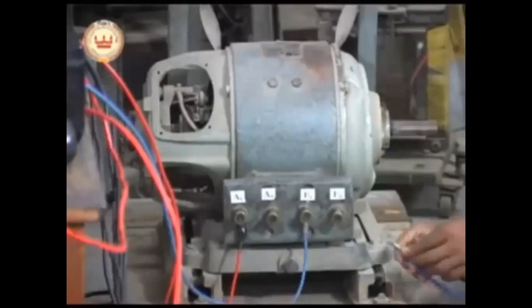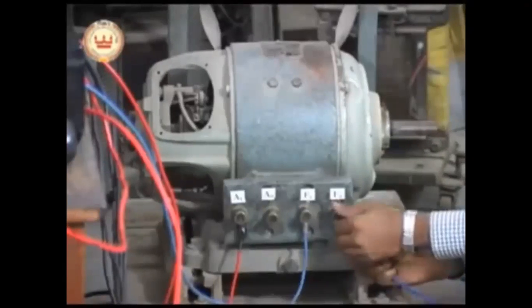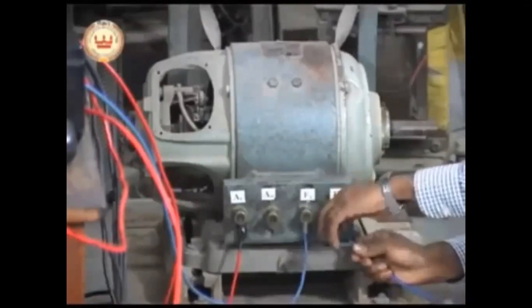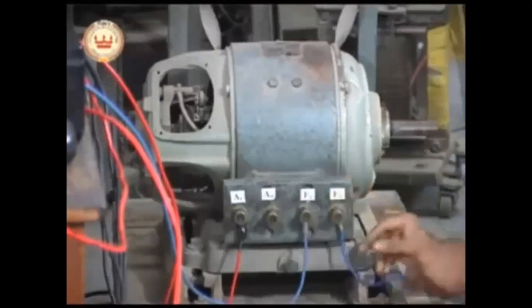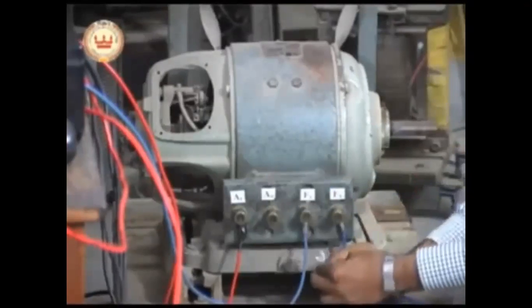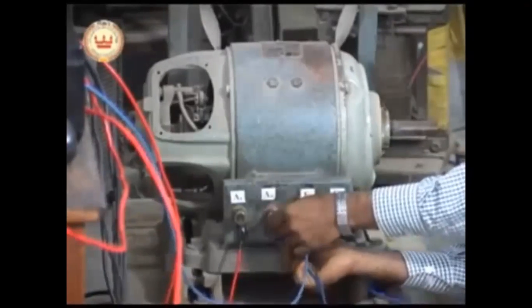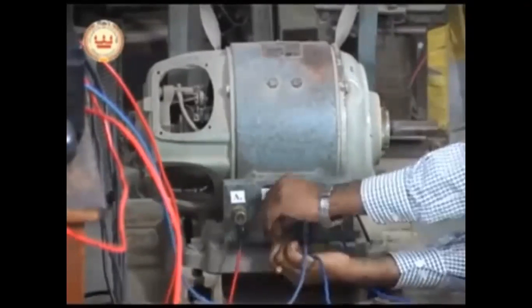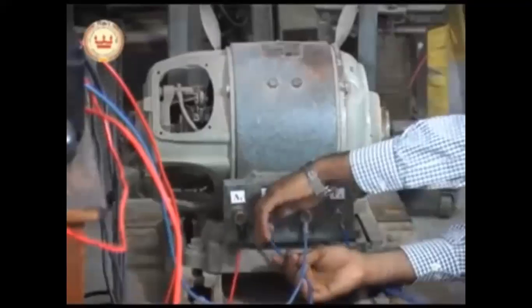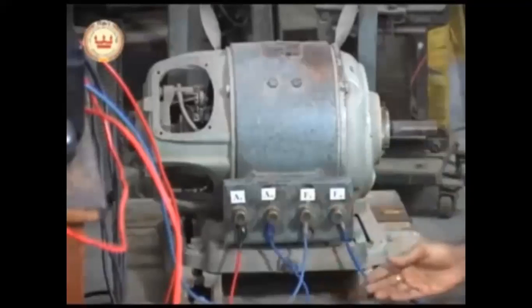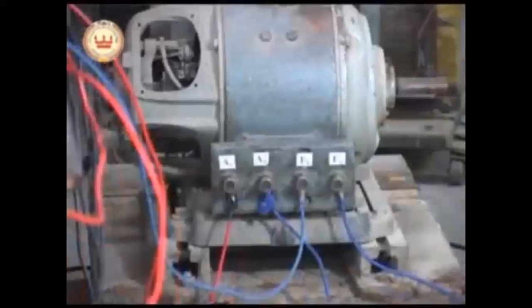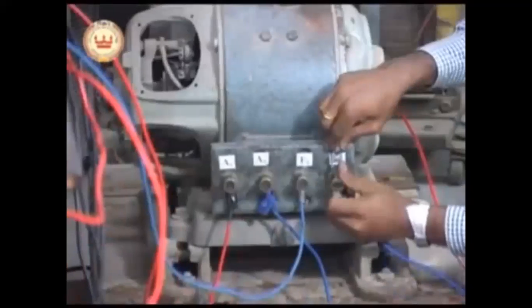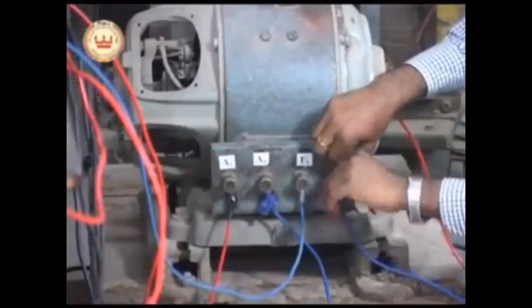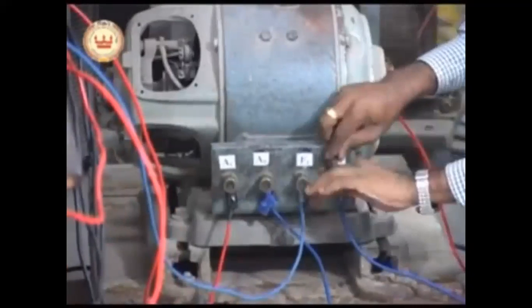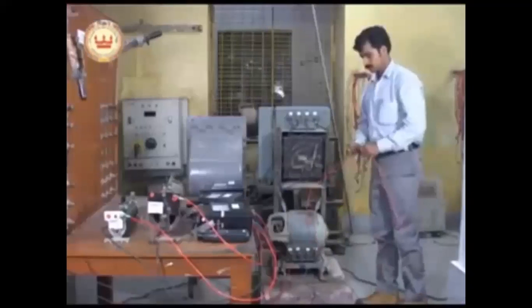Now short the A2 and F2 terminals of the motor and return these two shorted terminals to L1. The remaining two terminals of the armature and field coil will be shorted, and the shorted terminal will be returned back to the supply terminal L1. This shorting is returned back to L1 by this red wire.